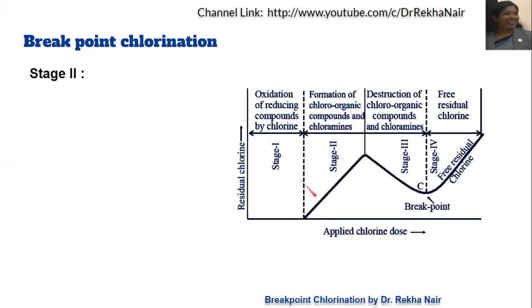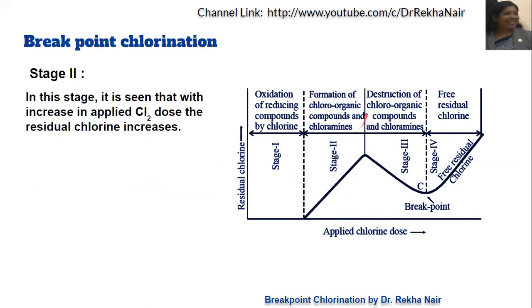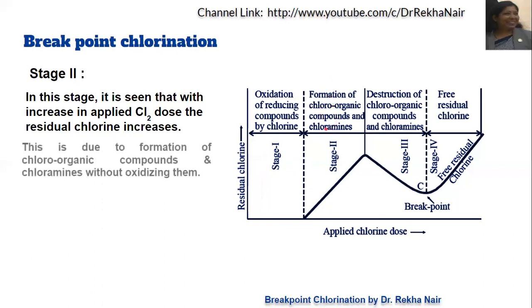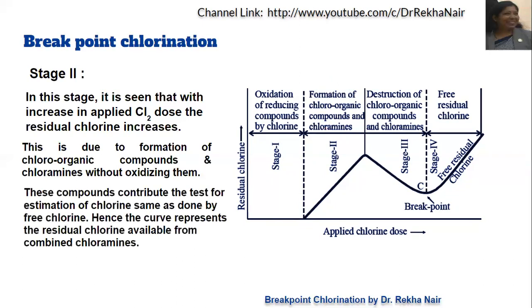In Stage 2, as we continue increasing the chlorine dose, there is formation of chloro-organic compounds and chloramines. The residual chlorine amount appears to increase continuously in Stage 2. This is because chlorine reacts with organic compounds and ammonia to form chloro-organic compounds and chloramines, and these compounds give a test result similar to that of chlorine, so it appears that residual chlorine is increasing.